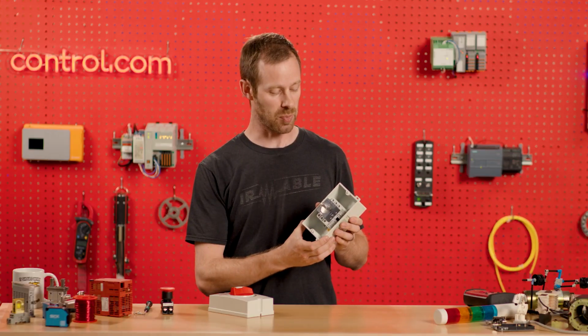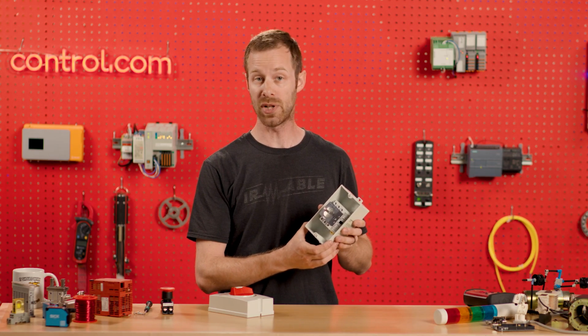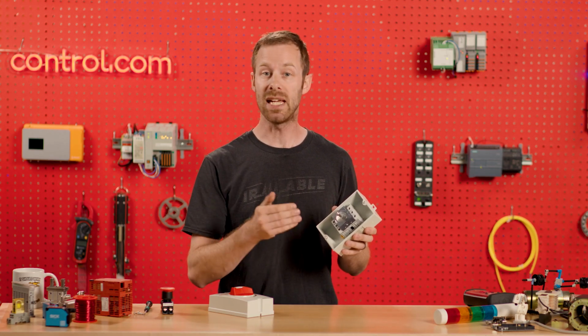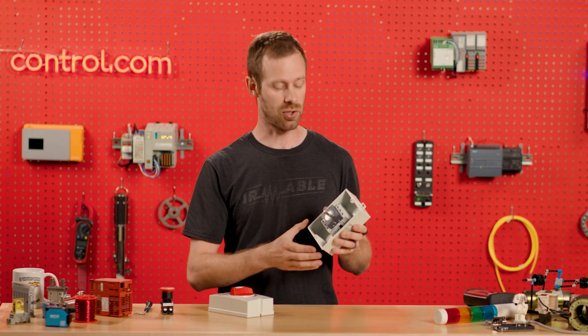Now, circuit breakers do have switches inside to be able to energize or de-energize them, but we don't often rely on those circuit breakers to be the main responsibility for switching on and off, because the sensitive springs and devices inside can, over time, with enough switches, change the current rating that it actually trips at.